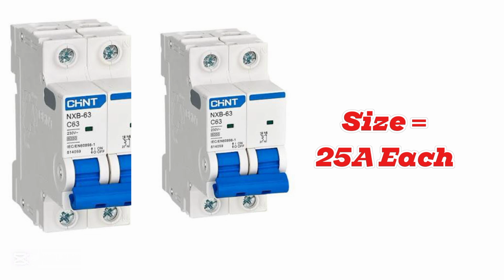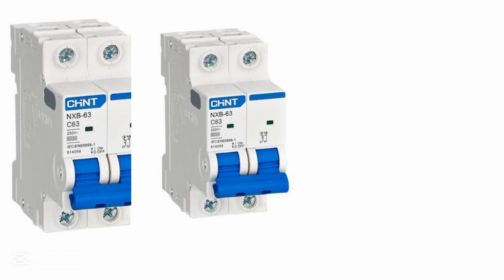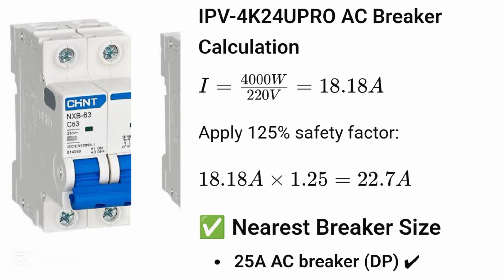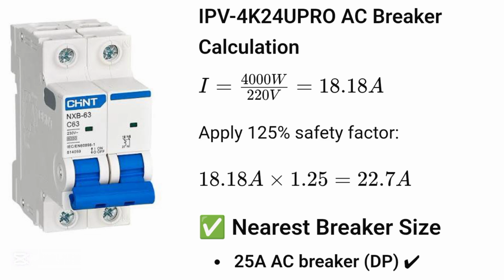We bought two AC breakers, one for AC in and the other for AC out. Both breakers are 25 amps. How do we arrive here? Like you can see, the inverters are 4000 watt inverters. So if we divide 4000 by 220, we have 18.18 amps. Now, if we oversize by 25% as a margin of safety, we'll multiply 18.18 by 1.25. We'll have 22.7 amps. Now, the closest breaker is 25 amps, which is exactly what we bought.